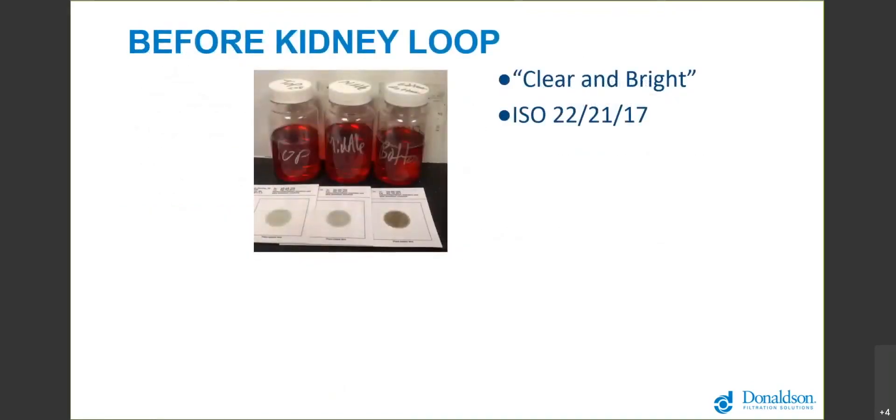We took samples of the tank before we started the kidney loop, the top level, the mid level, and the tank bottoms, and then visually inspected those bottles. They were all clear and bright, we didn't see a bunch of debris floating around and we didn't see any water in the tank.